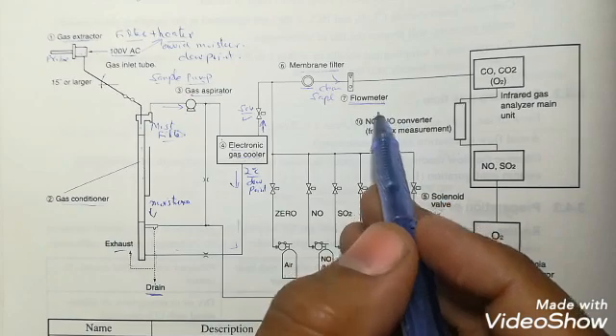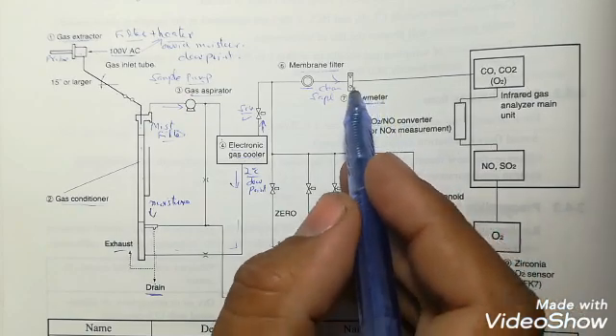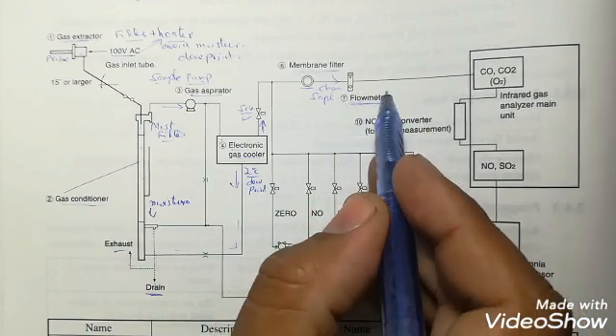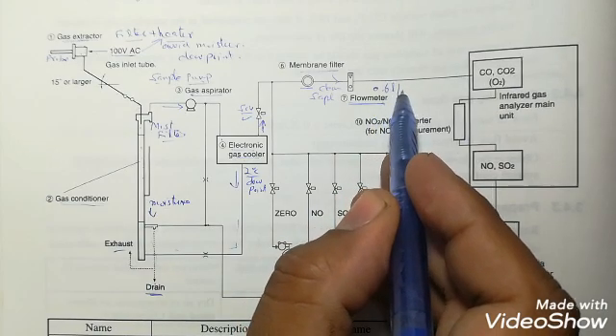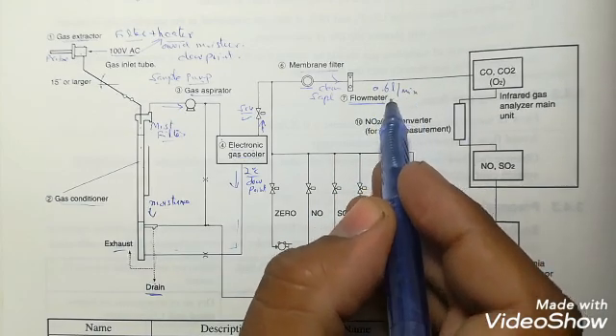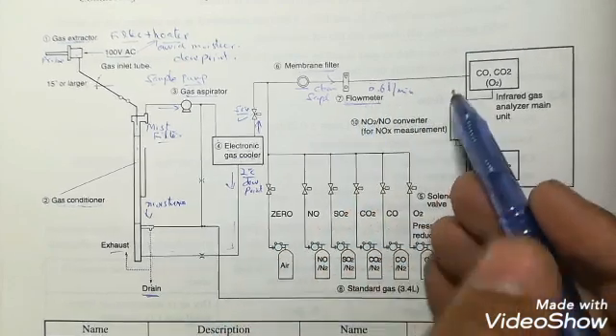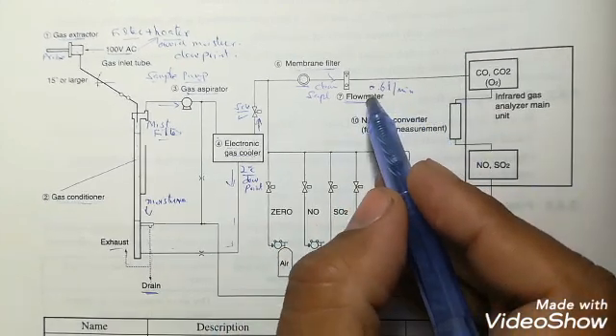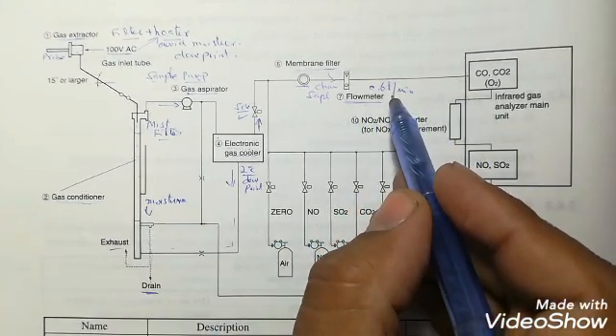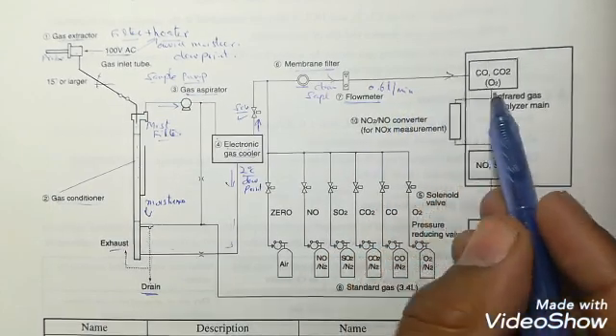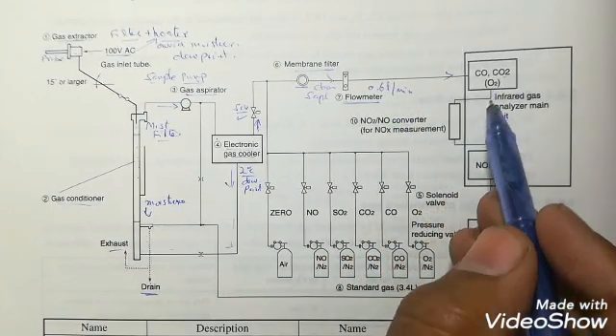This SOV is open when we are sampling. Then this sample goes to the membrane filter. It also cleans any remaining dust inside it, and then this is given to the module through this flow meter. Here we can adjust our flow to 0.6 liters per minute, which is the standard flow for this gas analyzer.